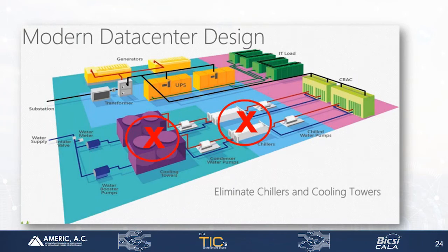You might be asking, why don't we need mechanical chilling? Well, OCP servers have much, much higher ingress temperatures than traditional proprietary servers - some like 55 degrees on the intake. Now lots of traditional data centers might be running air intake temperatures on the front of the racks at say 22 degrees - that's why you need all the chillers. And the chillers account for a very, very large amount of the overhead of the facility.